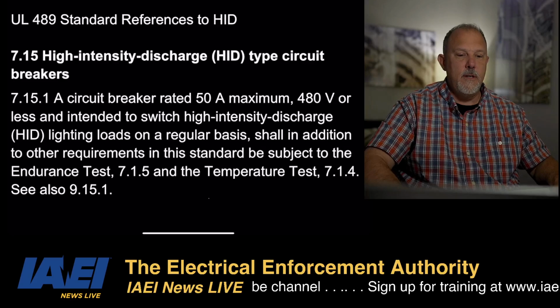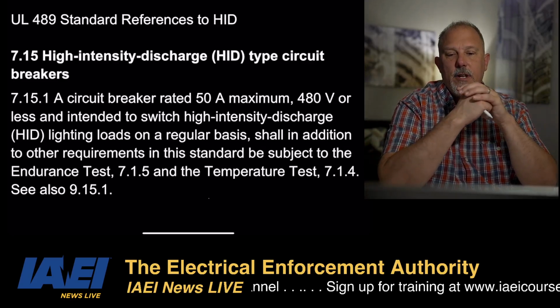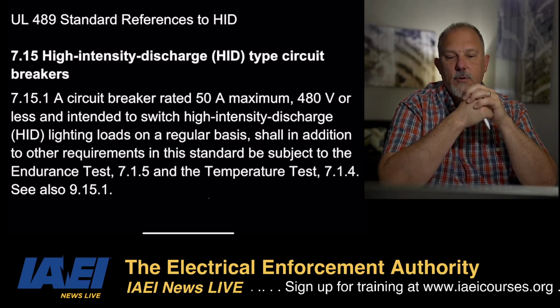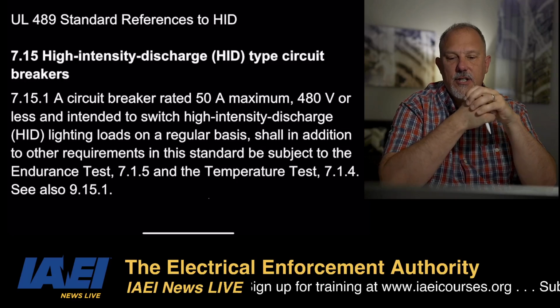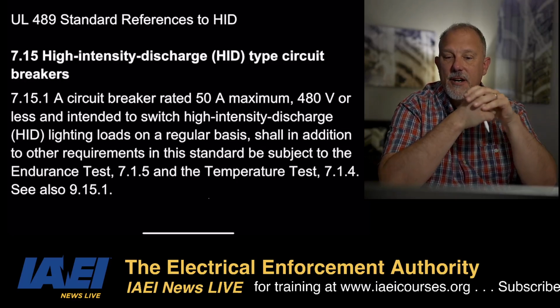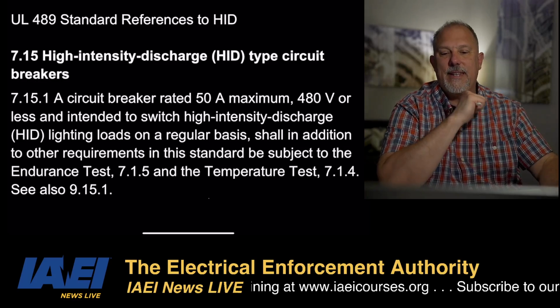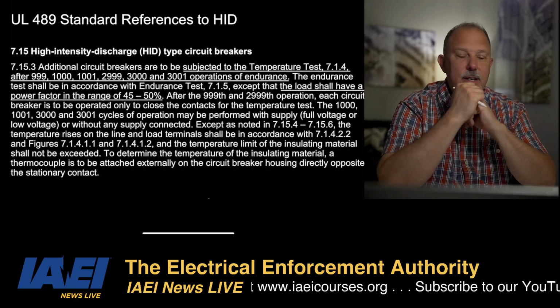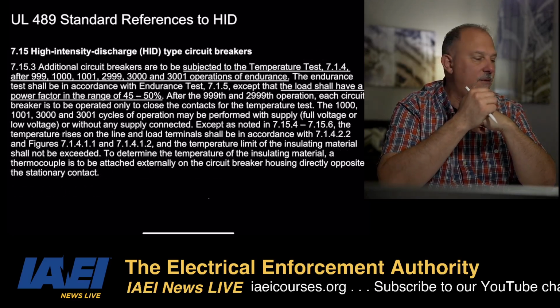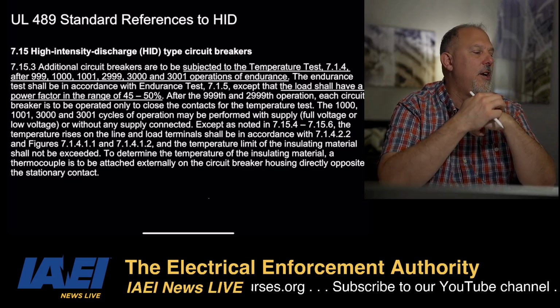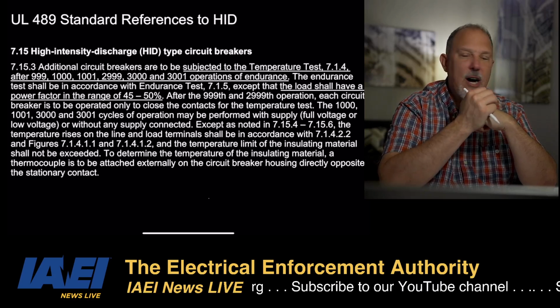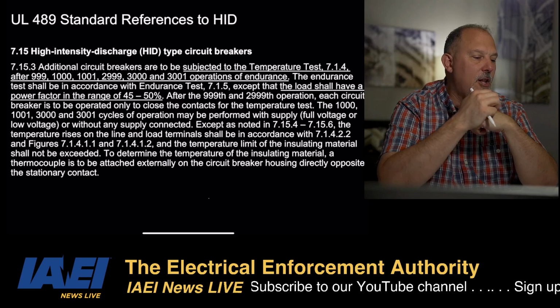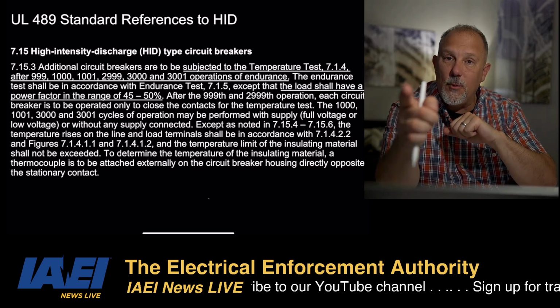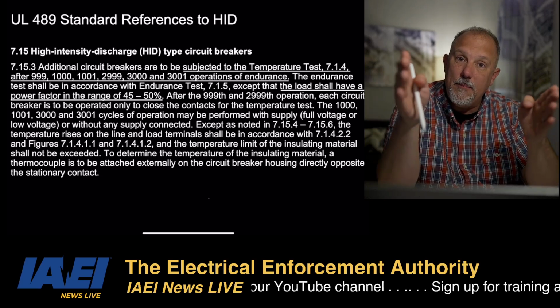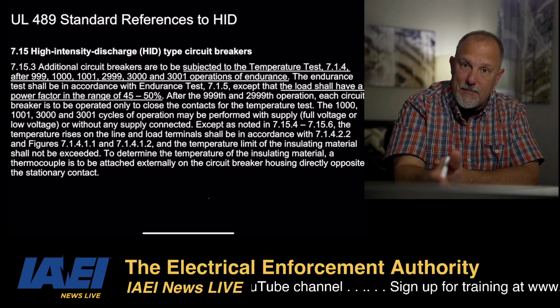So here's an example. 7.15.1: a circuit breaker rated 50 amps maximum, 480 volts or less, and intended to switch high-intensity discharge lighting loads on a regular basis shall, in addition to other requirements in the standard, be subjected to endurance tests and temperature tests. So look at this: subjected to temperature tests, 7.14, after 999, 1,000, 1,001, 2,999, etc. operations of endurance. The load shall have a power factor in the range of 45 to 50%. Remember I told you about the power factor. I'm looking at the current that I'm interrupting.